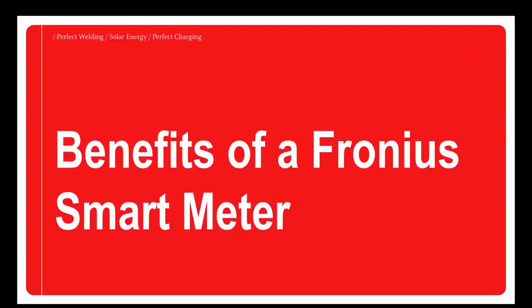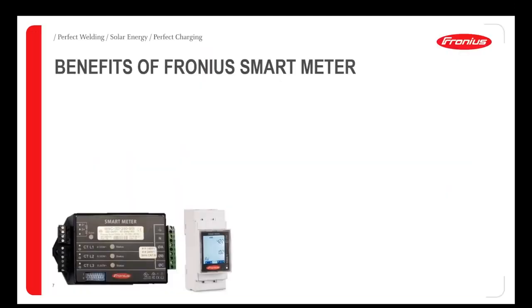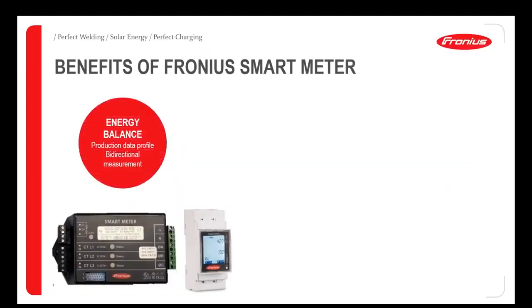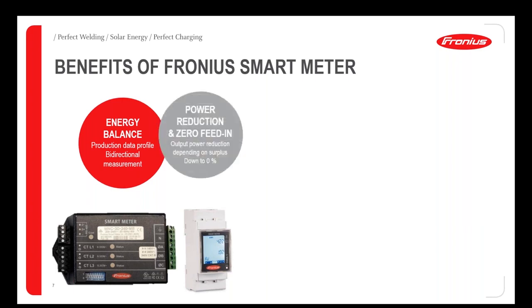So let's have a look first of all at the benefits of installing a smart meter. Of course, the smart meter enables you to record the energy flowing into and out of your building, meaning that we can calculate the energy balance. We can look at the consumption of all of your different loads within the building, and we can see the implication of having PV on that load. We can then control the export back to the grid. So feed in reduction, zero export control is all powered through having a smart meter installed.